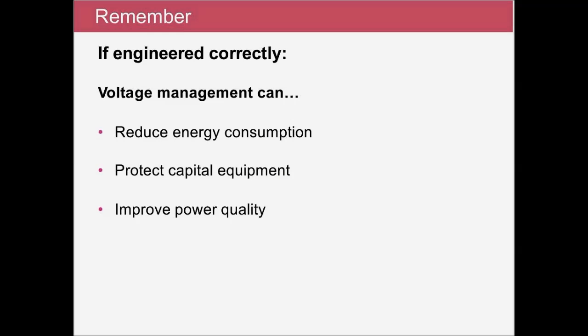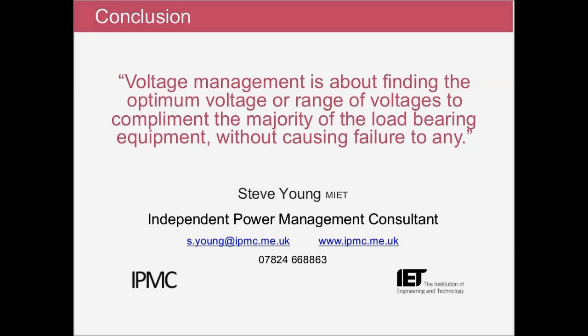So to summarise, if engineered correctly, voltage management solutions can reduce energy consumption, increase the shelf life of some load-bearing equipment, and improve the quality of the power coming both in and out of the installation. So remember, voltage management is about finding the optimum voltage or range of voltages to complement the majority of the load-bearing equipment without causing failure to any.